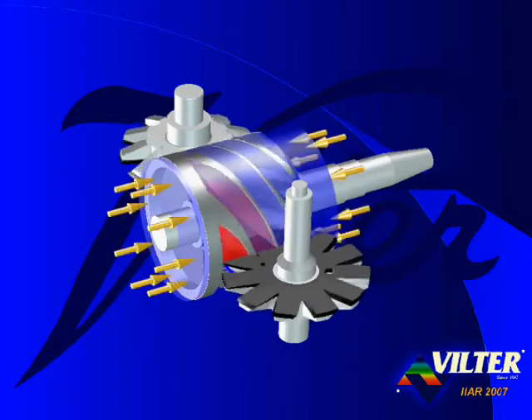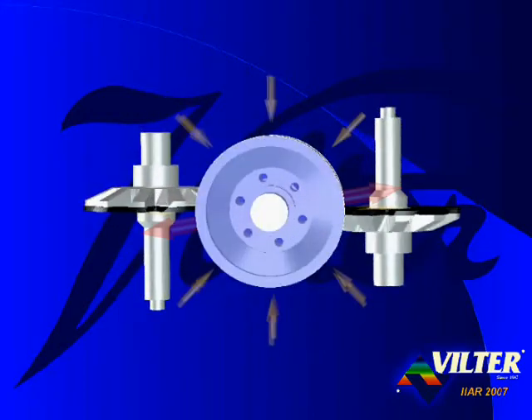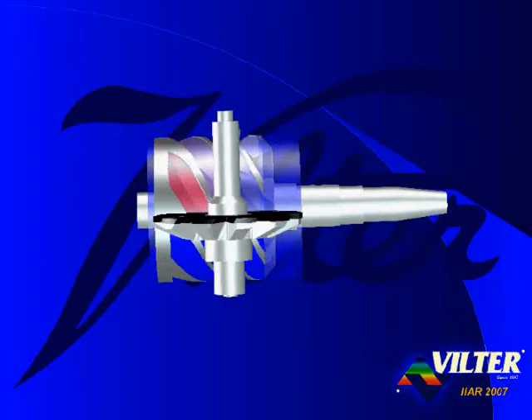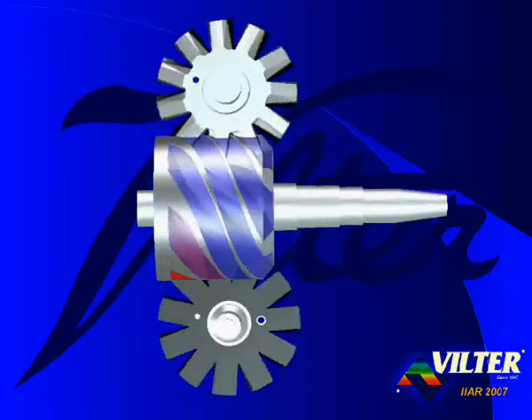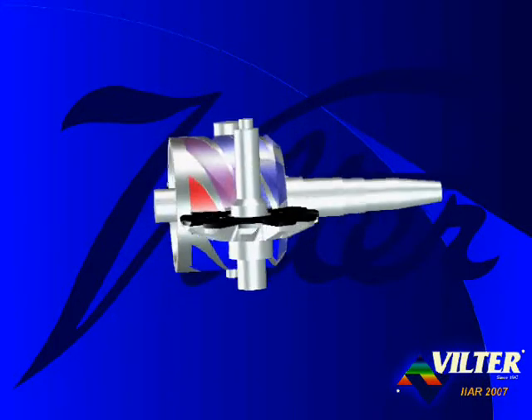Vent holes through the main rotor allow both ends to be at suction pressure for balanced axial forces. Dual gate rotors result in balanced radial forces. Balanced radial and axial forces allow Vilter to offer a standard 15-year bearing warranty.